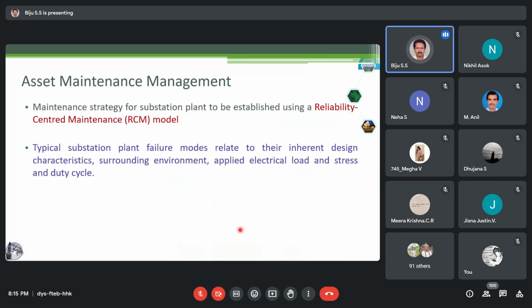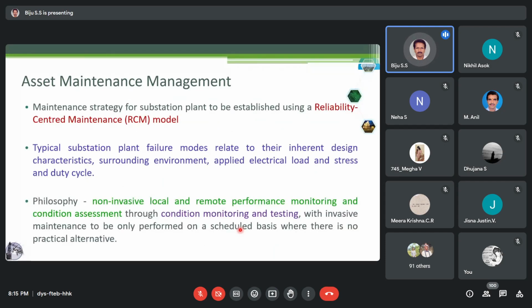Now, maintenance strategy for substation. This is a relatively new one. Usually nowadays, the maintenance strategy is based on the reliability-centered maintenance model, RCM. What you do is, even if an asset is flagged for maintenance, the system will look into how critical this asset is for a network, so how critical it is for the reliability of a network. Based on that, it will prioritize the maintenance activities. So that is called reliability-centered maintenance.